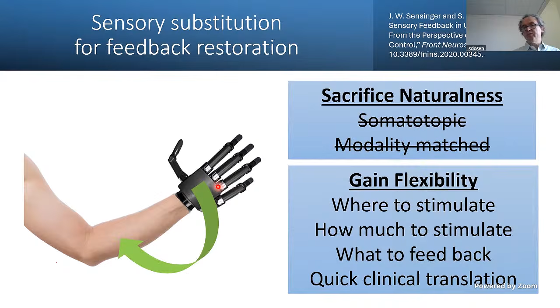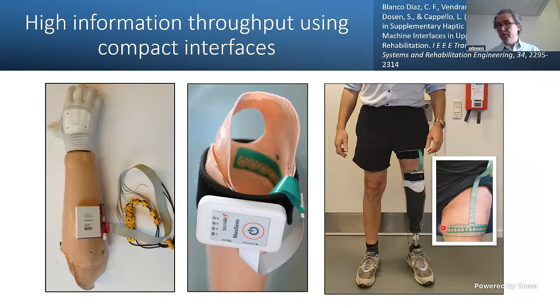And I will give you a couple of examples that sort of emphasize this flexibility that we have with this particular approach. So the first is that we have freedom to take many stimulation channels, and we can place these stimulation channels all around the residual limb. So we can stimulate the residual limb in many points. And these are the systems that we developed in our group together with our collaborators. So for instance, this system uses an array of vibration motors that you can see here. Then in this case, we have an electrode that is placed in the socket for an upper limb prosthesis user for electrotactile stimulation. And then we have a very similar system, but in this case, the electrode is placed on the residual limb of the lower limb prosthesis user, a transtibial prosthesis user in this particular case. So we have many stimulation points that we can use to deliver rich stimulation profiles.